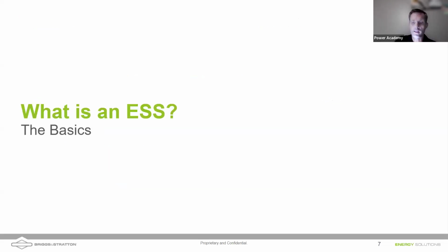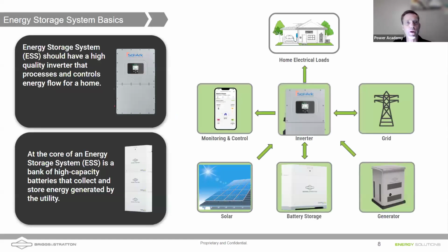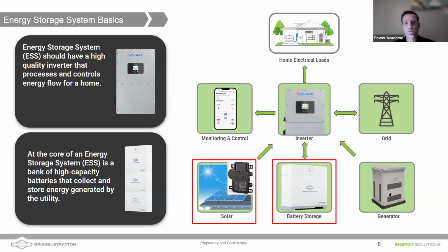We're going to start first at the basics of what an ESS is, and then we'll point out exactly what we're talking about with AC coupling. So an energy storage system with solar typically reflects the inclusion of a battery system, right? Energy storage here means that there's a battery capable of storing energy coming from potentially a solar array. It could just be coming from the grid and charging that battery, or it could be coming from a generator. So at the heart is a high-end battery like the Briggs & Stratton stackable battery that you can see there. An inverter is also needed to transform the DC power from the battery into usable AC for AC appliances in the household, or to sell that extra energy back to the grid if you're using solar and you have an interconnection agreement.